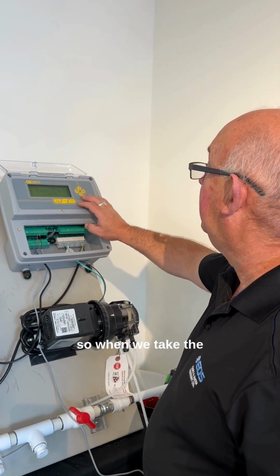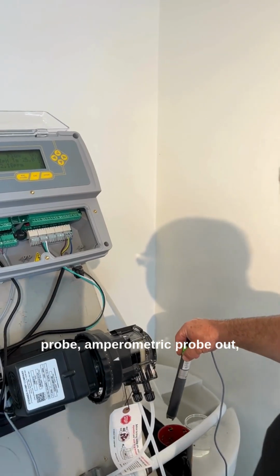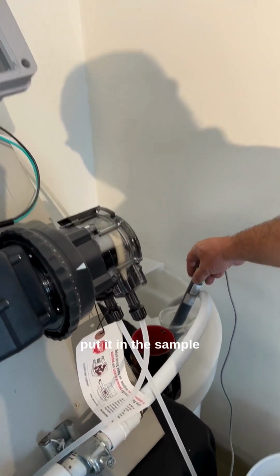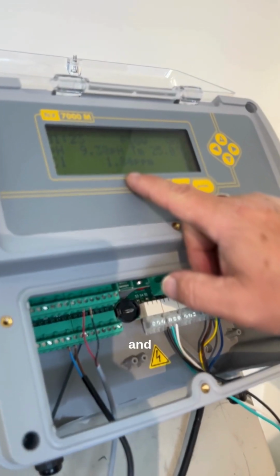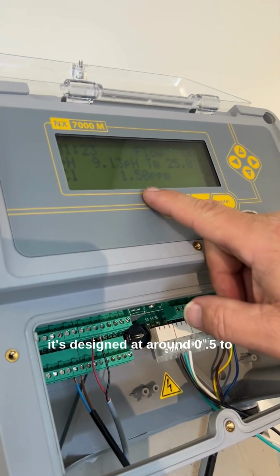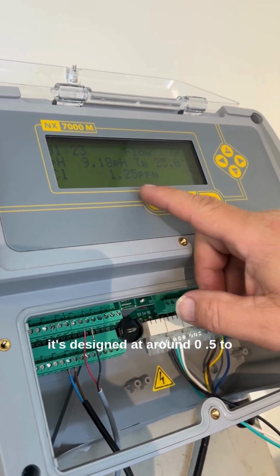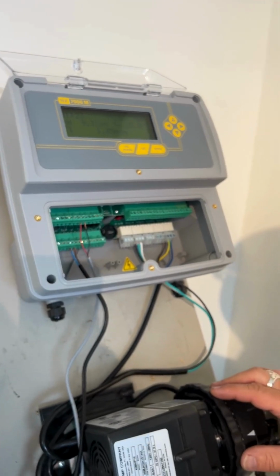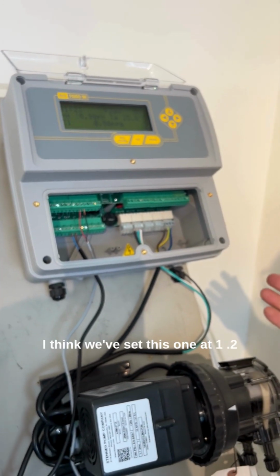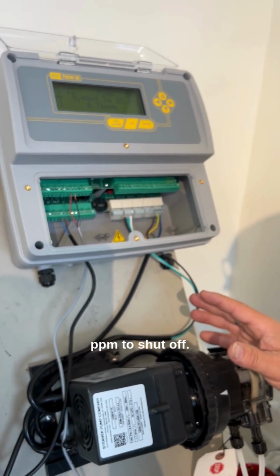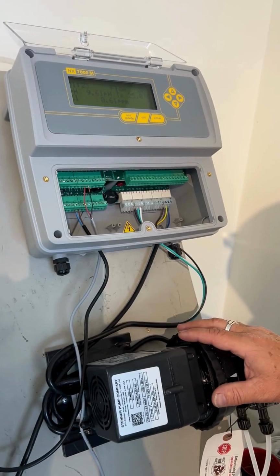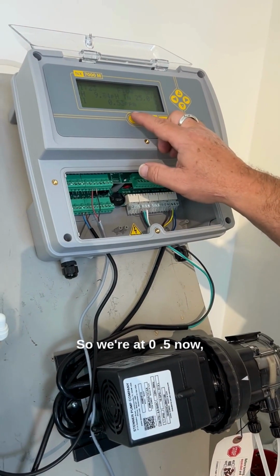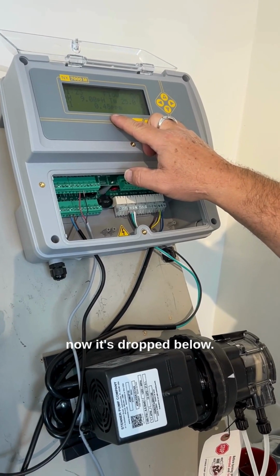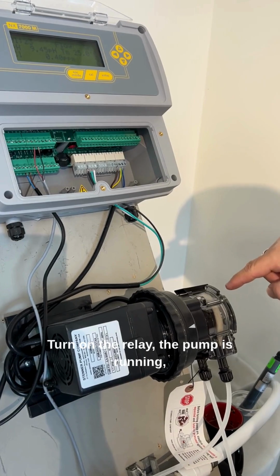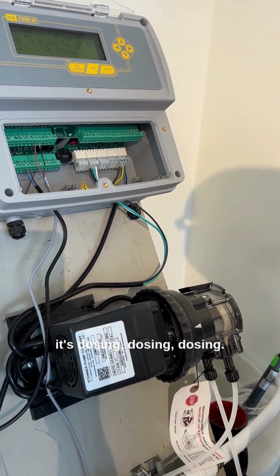Okay? So when we take the amperometric probe out and put it in the sample that has no chlorine in it, we can see it's starting to drop now. It's designed at around 0.5 to turn on. And it'll build up to, I think we've set this one at 1.2 ppm to shut off. So we're at 0.5 now. Now it's dropped below. Turn on the relay. The pump is running. It's dosing.